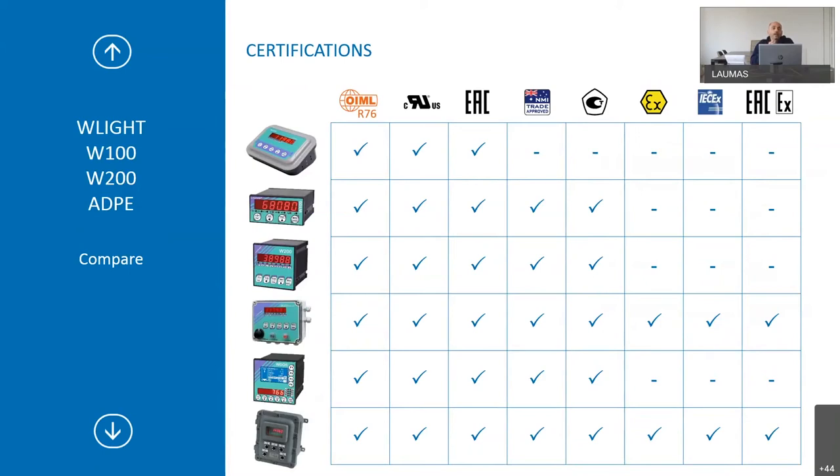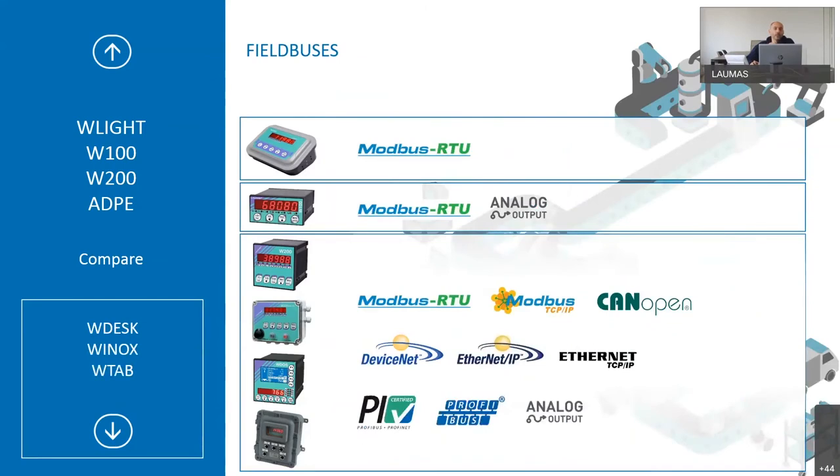Here is a summary comparing certifications across indicators: OIML R76, UL for the United States, EAC, and others — displayed for better understanding. You can also see all field buses available for the base and batching indicators. For WLIGHT, only Modbus RTU is available via serial port. For W100, you can have Modbus RTU and analog output. For the other indicators, all field buses described at the bottom of the slide are available.